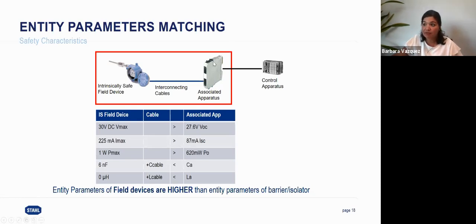My barrier also has a set of entity parameters, and it's saying that in normal or abnormal operation, the barrier will be able to pass up to 27.6 volts, up to 87 milliamps. So we make sure the maximum amount of energy the barrier could pass is less than the energy the field device can handle, right? If I have a table that can hold 100 pounds, I'm not going to put 120 because I'm going to break it, right? So that's what we're trying to do. The barrier will go same or lower.